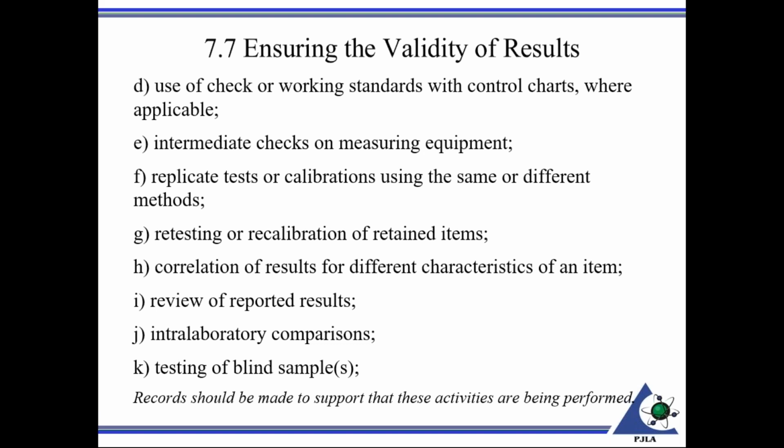Also, it could alleviate a risk of perhaps having to go back and do an investigation if the equipment was out of tolerance when you submitted it back for recalibration. If you have a good system of intermediate checks that perhaps can be used to discover it before equipment was to drift, or perhaps cut down on the amount of impact analysis that needs to be done.